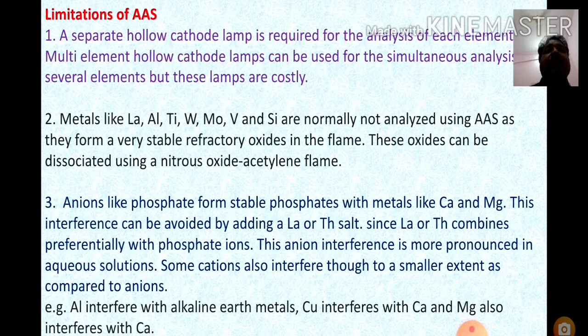Third limitation, anions like phosphate form stable phosphates with metals like calcium and magnesium. This interference can be avoided by adding a lanthanum or thorium salt, since lanthanum or thorium combines preferentially with phosphate ions. Then this interference can be removed. This anion interference is more pronounced in aqueous solutions. Some cations also interfere, though to a smaller extent as compared to the anions. For example, aluminum interferes with alkaline earth metals, copper interferes with calcium, and magnesium also interferes with calcium.